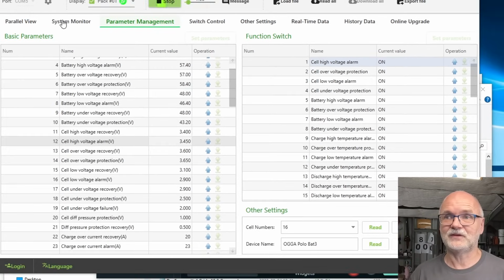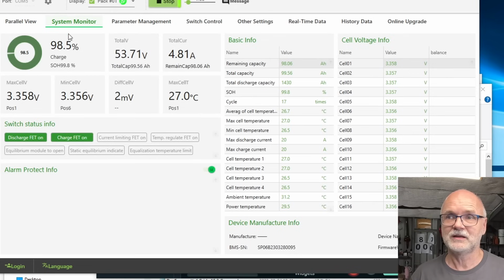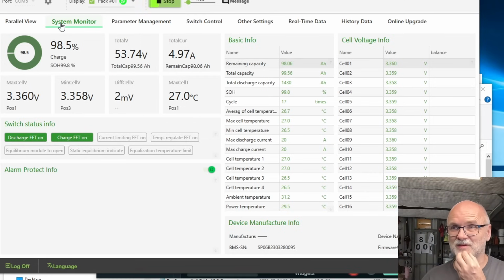But I was going to see if this has actually improved now with the new firmware, but I don't think it has, because we are still at 98.5%, which we were like 45 minutes ago. The battery is still charging. We've got no alarm. And look at this, all the cells are under 3.36 volts. This is our highest, they're all under that. The state of charge does not change anymore. It does not move. So this battery will stay at 98.5% forever now until it's fully charged. So at the moment I cannot really see an improvement over the older firmware version in terms of showing the correct state of charge. It was linear all the time until you hit 98.5%.